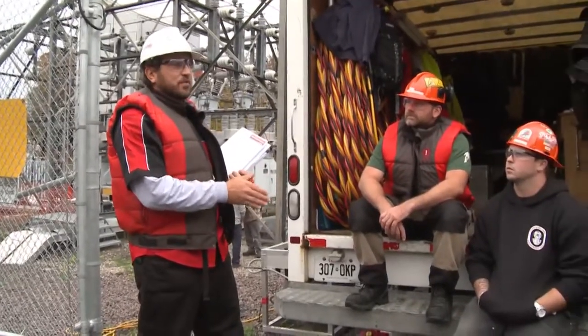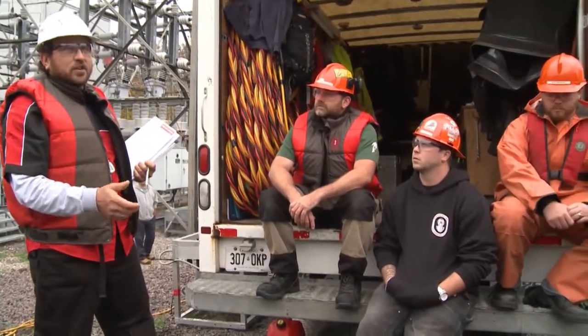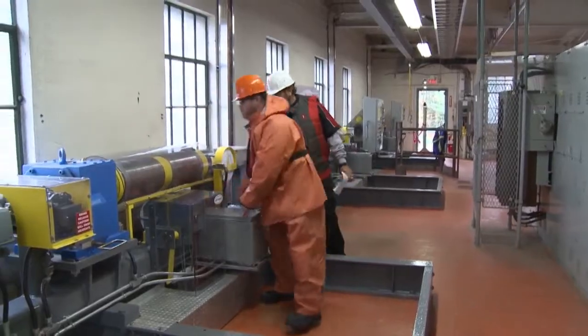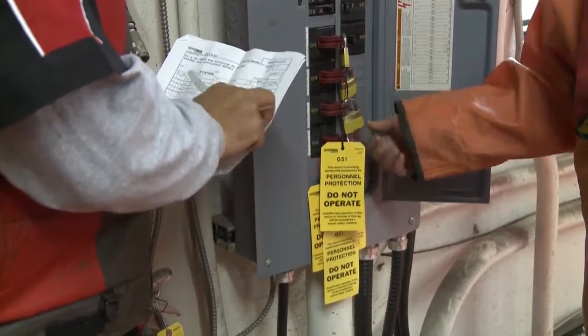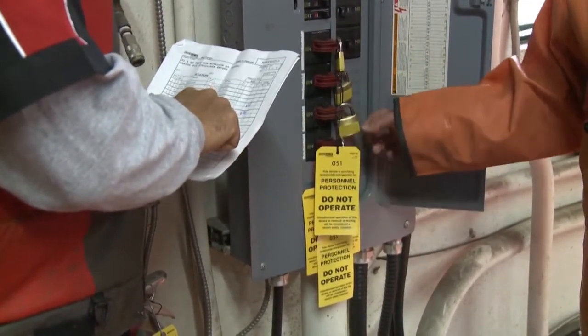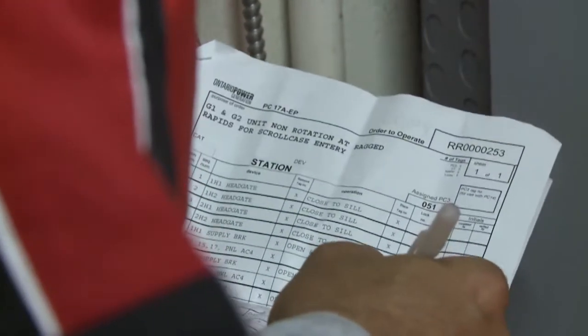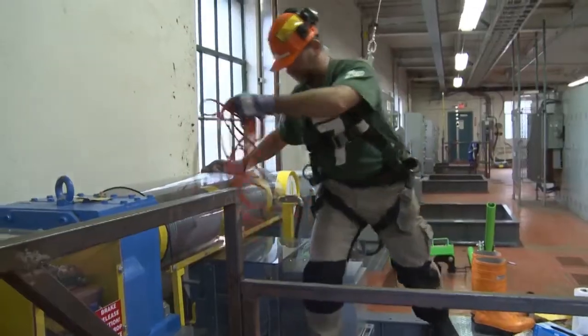Let's concentrate on limiting the diver's movement to protected bays. Workers have a duty to ensure that they know what their working environment is going to be and that all safety measures and procedures are in place. Lock number 8 should be head gate 2 supply. Lock number 9 is a second head gate 1 supply breaker. Tag number 51 for permittory, lock number 10, 051. Workers need to be instructed and informed on the operational plan as well as the contingency plan prior to starting any work within that diving operation.